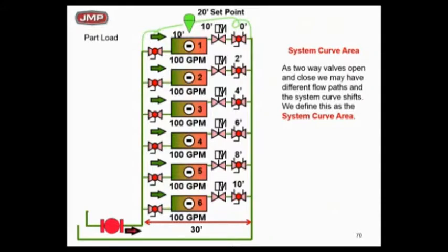Those two-way valves closest to the pump need less head than those two-way valves furthest from the pump. It's called a direct return system, what we've been dealing with for years. Now, let's plot that and see what that means.